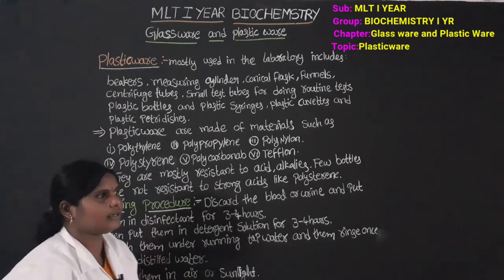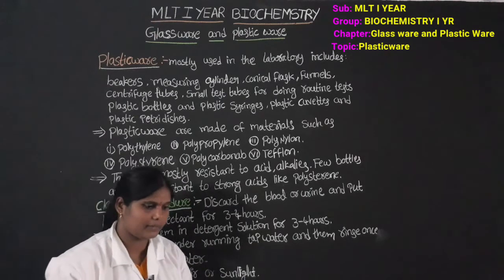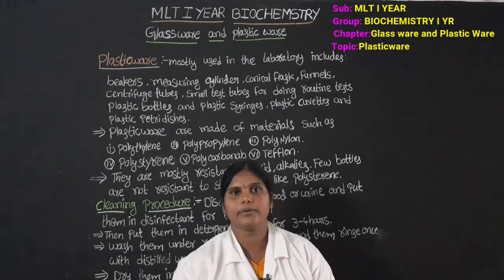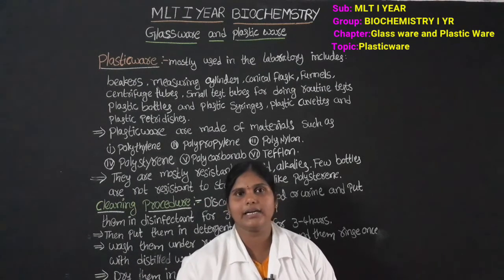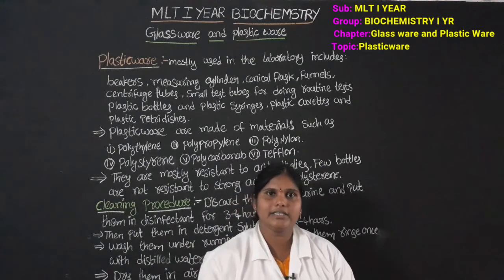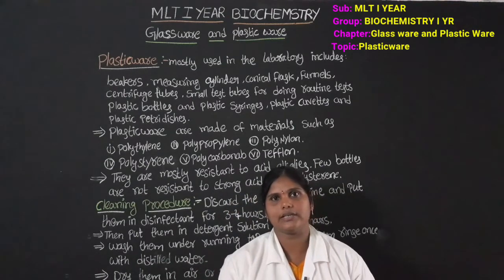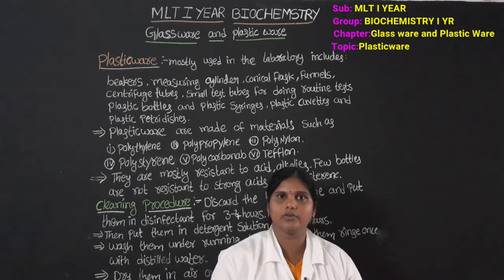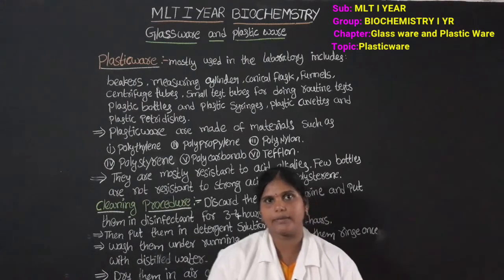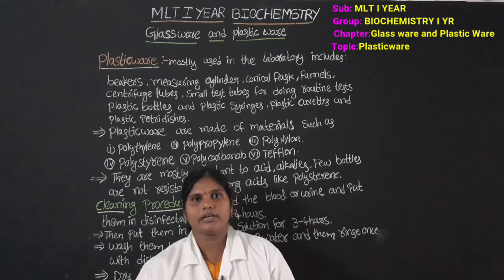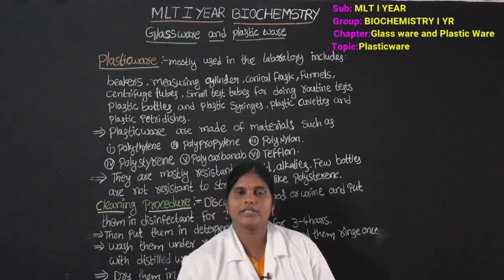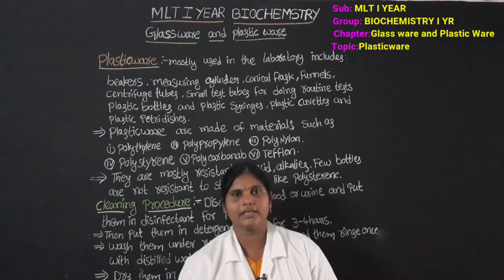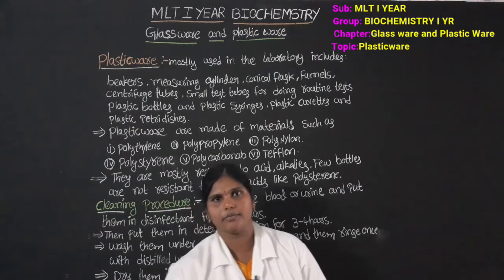Cleaning Procedure for plasticware: First step — after using plasticware with blood or urine samples or reagents, soak them in disinfectant for 3 to 4 hours. Then, remove from disinfectant and place in detergent solution for 3 to 4 hours. Next, wash under running tap water with brushing. Then rinse with distilled water once. Finally, dry them — either air dry or dry in sunlight.